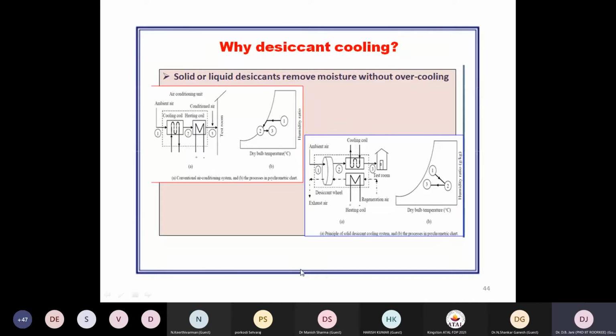Typically, the desiccant cooler in the system will be made from a matrix that is lined with some chemicals known as desiccant materials. Suppose we talk about refrigerants first. A refrigerant is a special group of chemicals having a boiling point very much lower than normal temperature. Suppose we talk about ammonia as the refrigerant: its boiling point is around minus 33 degrees. At minus 33, ammonia will convert from liquid to vapor form. But if you want to store it at ambient pressure and temperature, we have to raise its pressure to raise the boiling point above normal atmospheric ambient conditions. So its property is a very low boiling point.